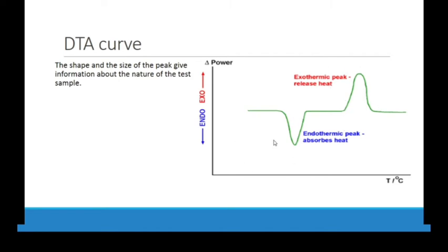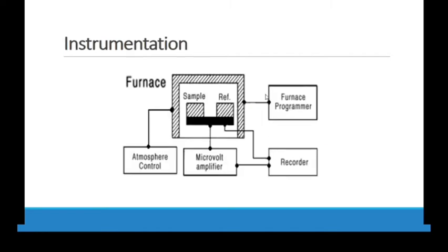If we talk about the instrument, it looks similar to your DSC setup. You have one sample pan, one reference pan, and a furnace which controls the temperature. There is also an atmosphere control used for gases — you must introduce or purge nitrogen, which is an inert gas, to remove oxygen or any other gas that can react or alter the temperature of the furnace. The output is then recorded through a micro recorder.